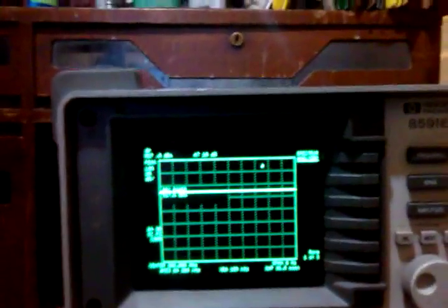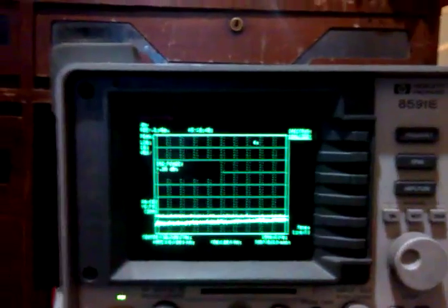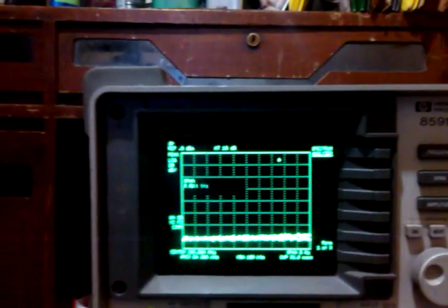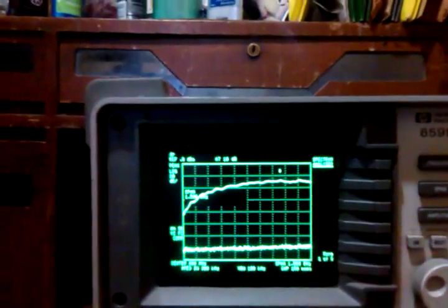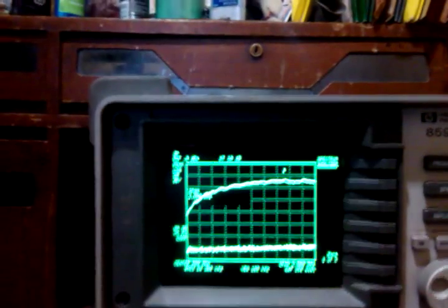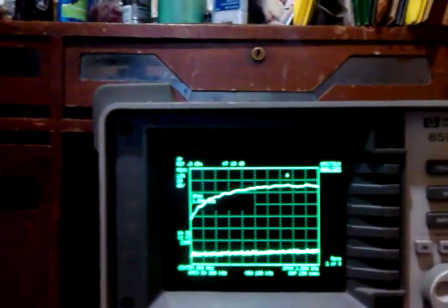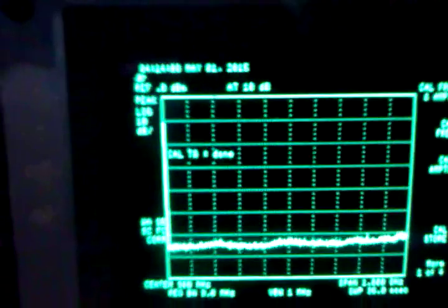Okay, it's now self-calibrating, calibrating the output from the tracking generator towards the input of the spectrum analyzer. SRC power checking in, span checking the span. Okay, so it was a success. It says here CAL TG, which stands for tracking generator, done.